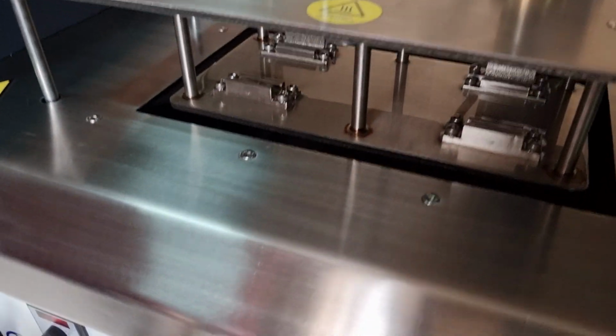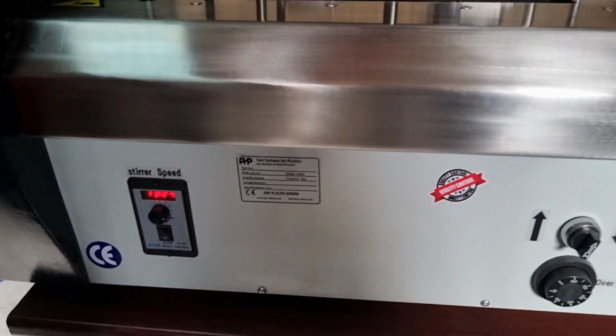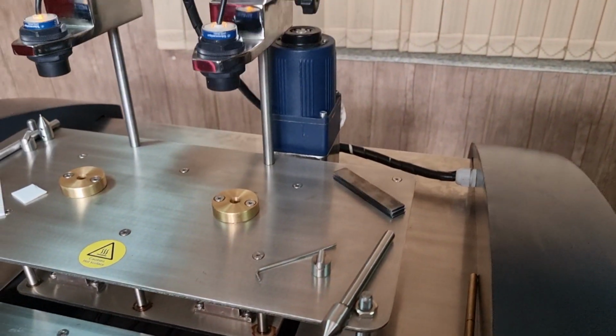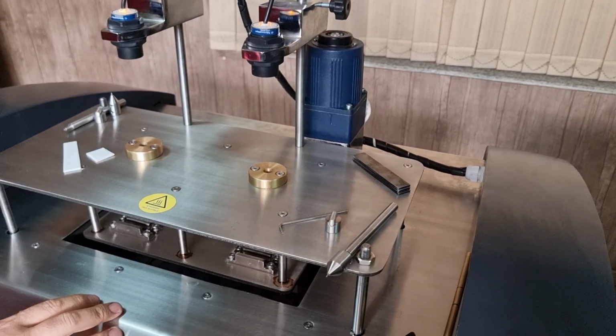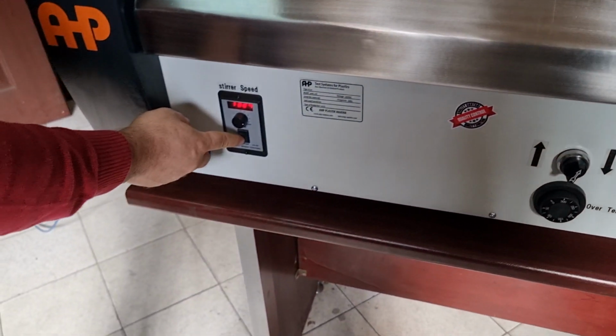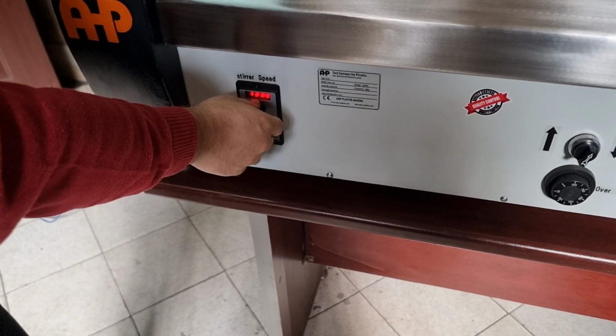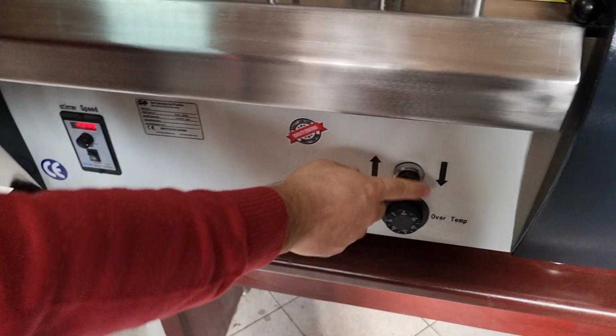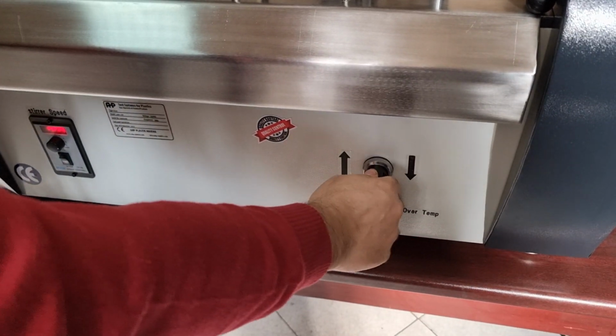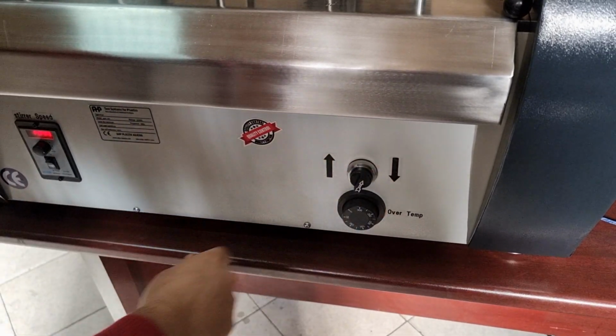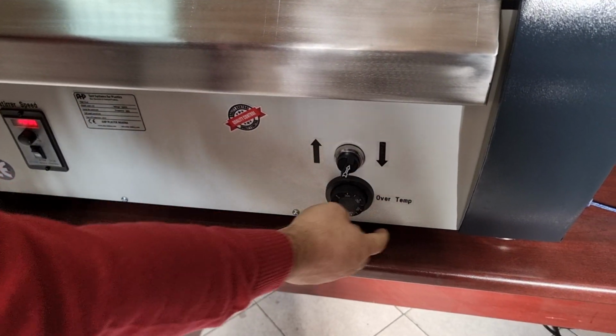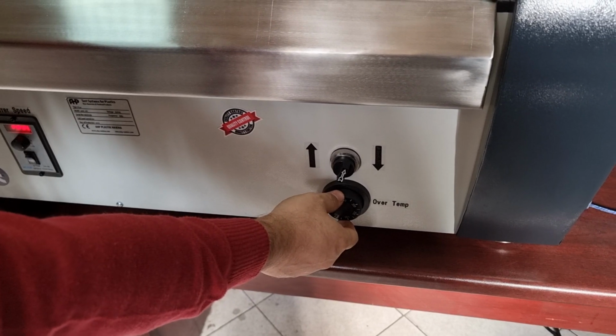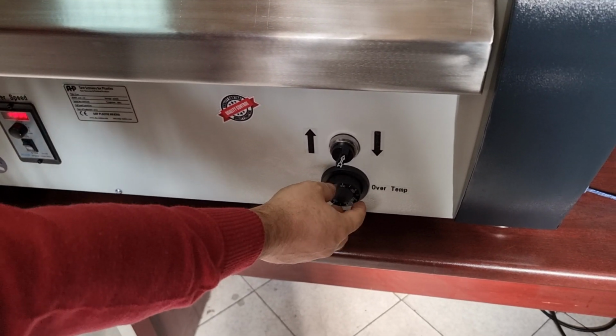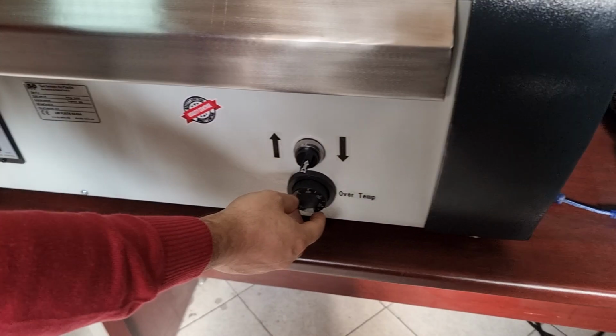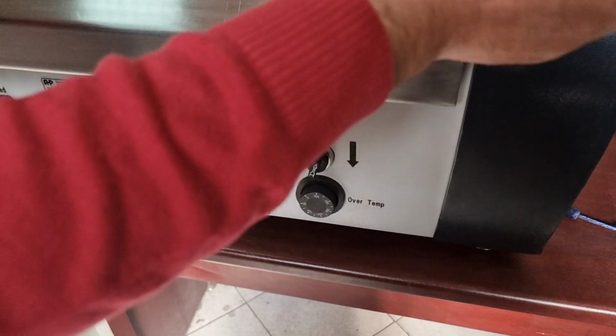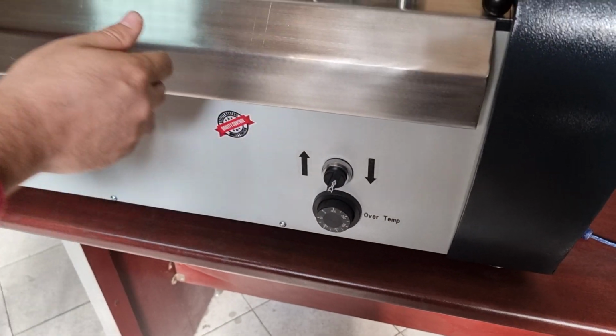Here in the front panel, you have the stirrer speed. You have a stirrer here for the homogeneous temperature of the oil inside the bath. You can easily turn on and off and adjust the speed of the stirrer here. You have a pneumatic elevator key here. You have over temperature protection. It's the thermostat for controlling the maximum temperature of the heating element in case of failures and electronic parts.